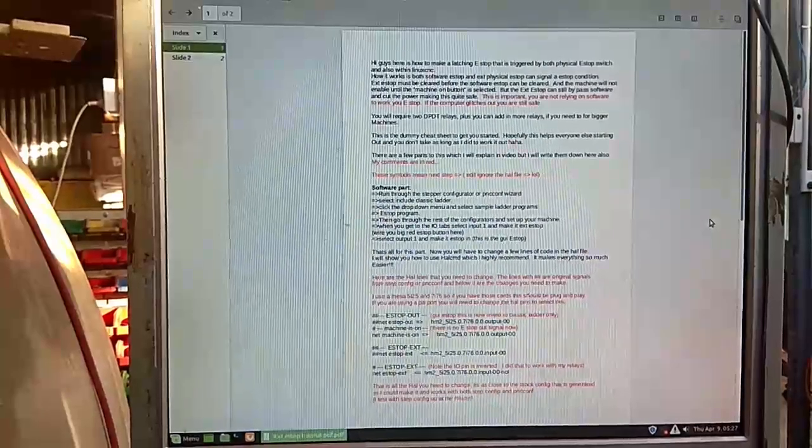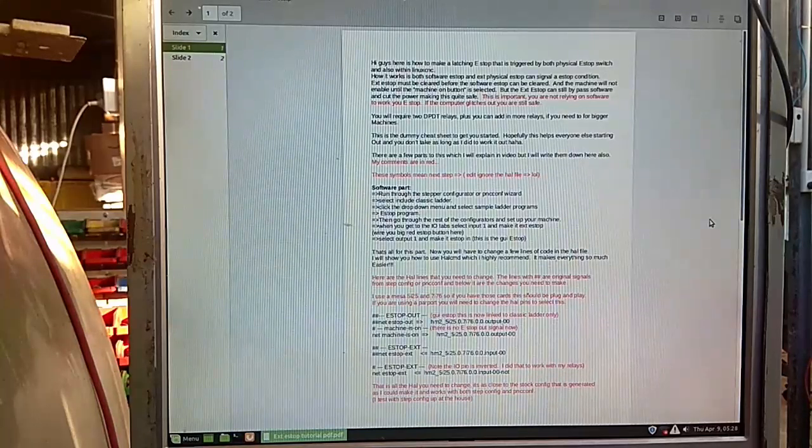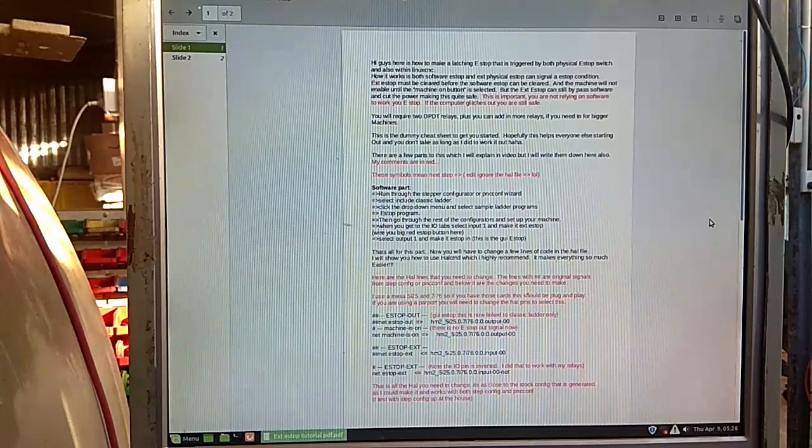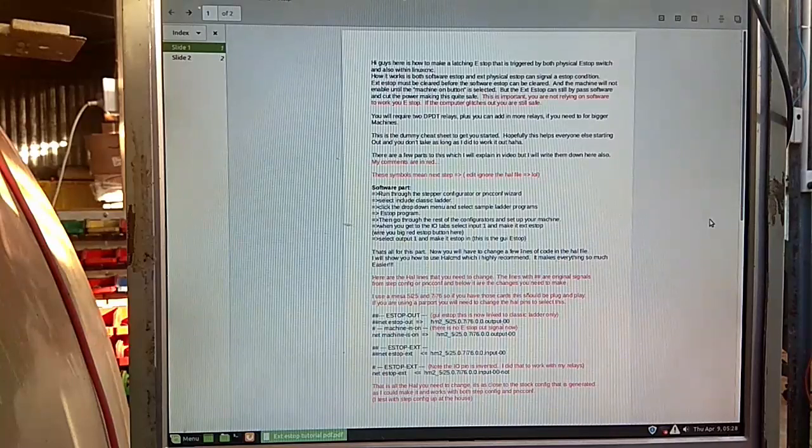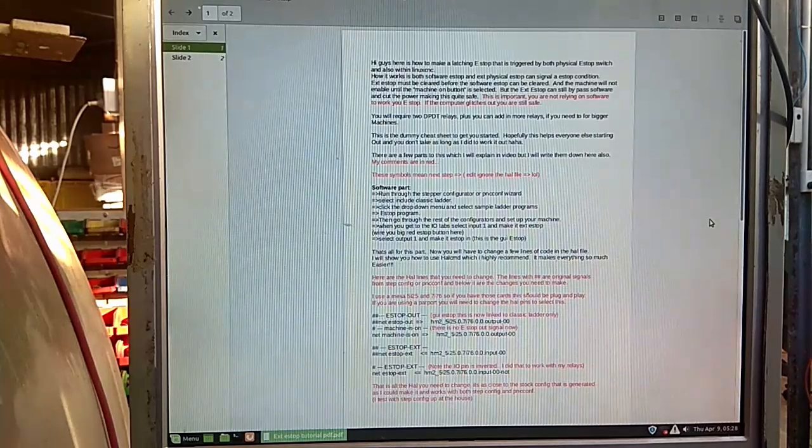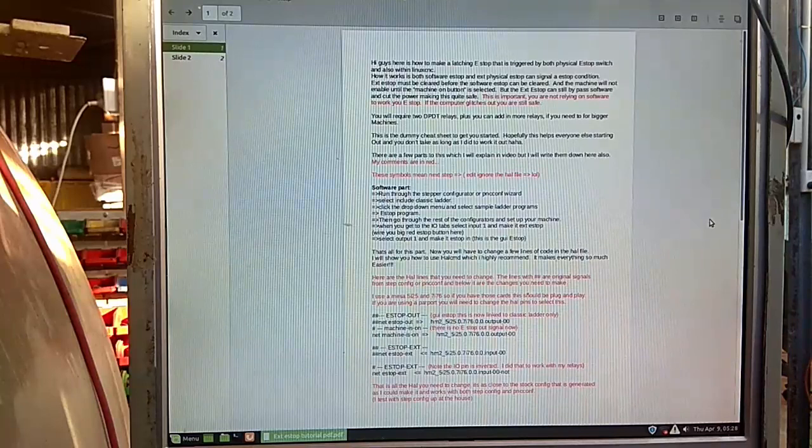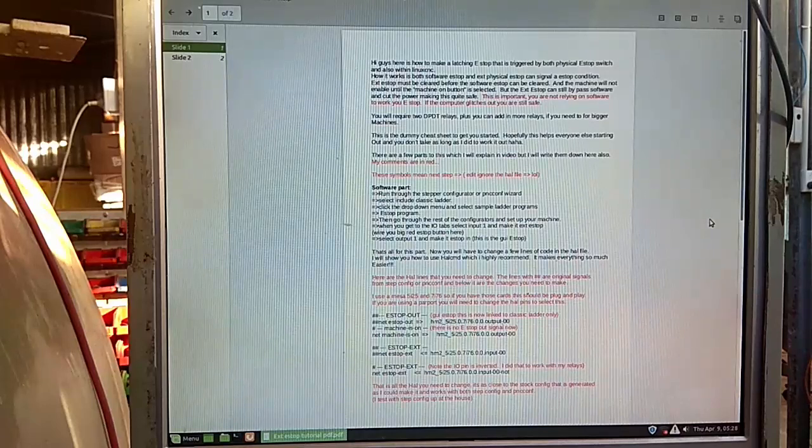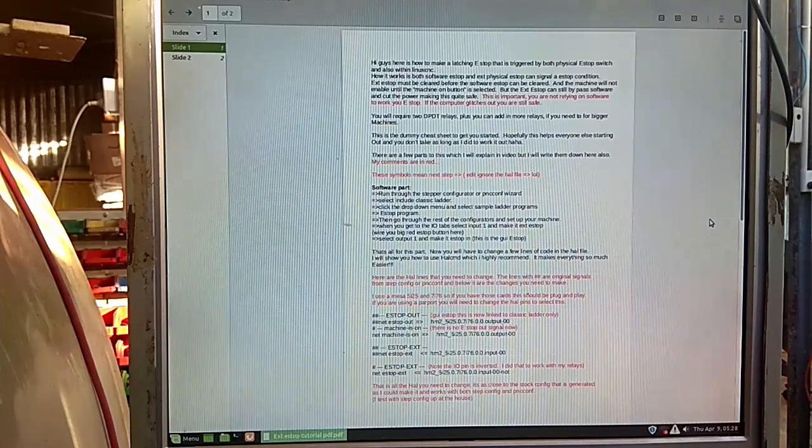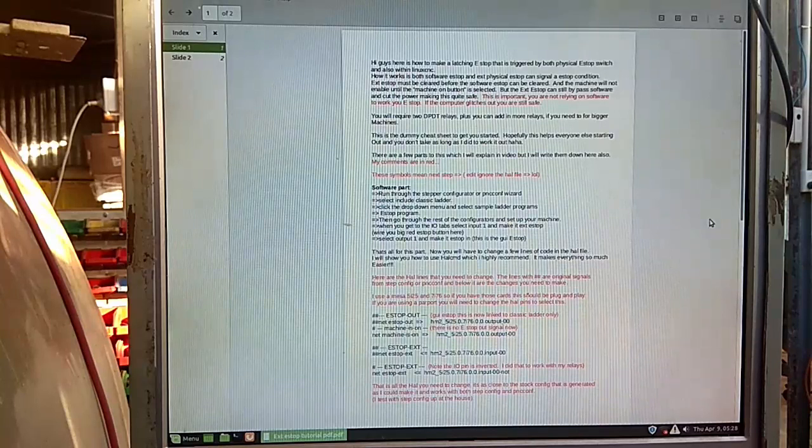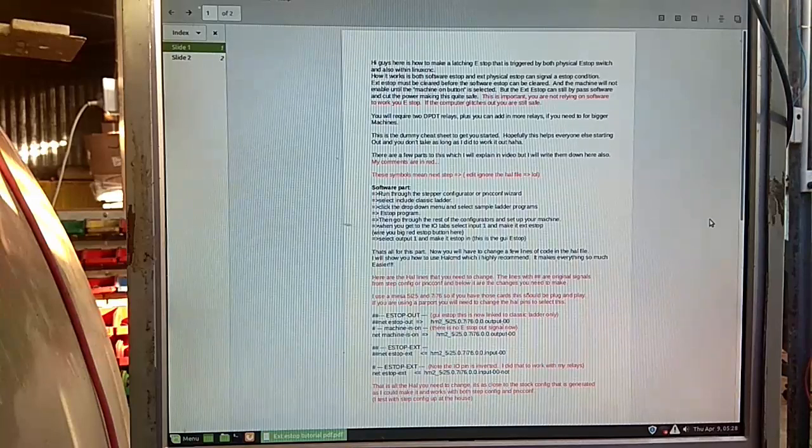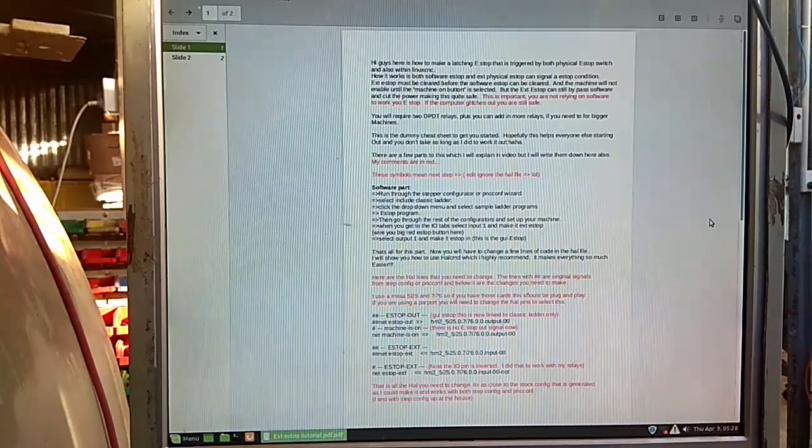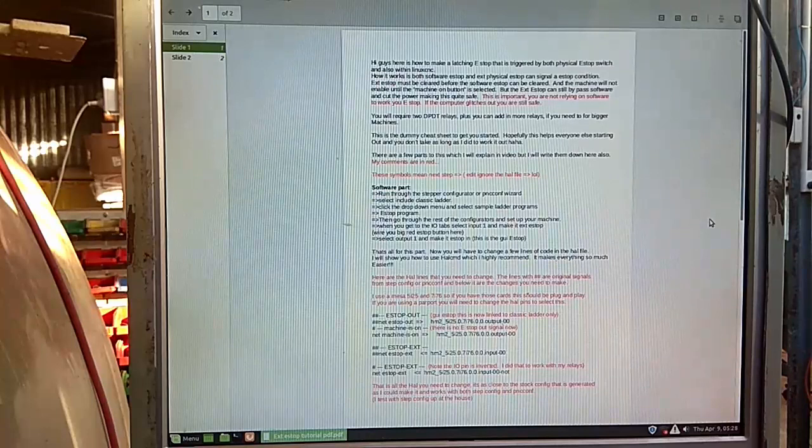Hi guys, I wanted to make a quick video, not so quick video, about how to interface an external big red e-stop button into Linux CNC within Classic Ladder, so that everything is interconnected. When I hit the e-stop, power is removed from the machine so it's safely thrown into e-stop. But then also when I run into an e-stop condition in the software, it also kills the power. The two e-stops are interfaced so that I cannot turn the machine back on until both e-stops are pulled out.